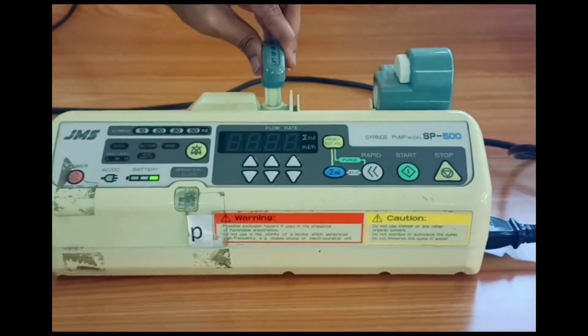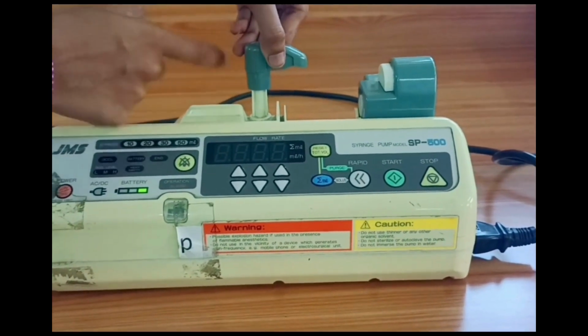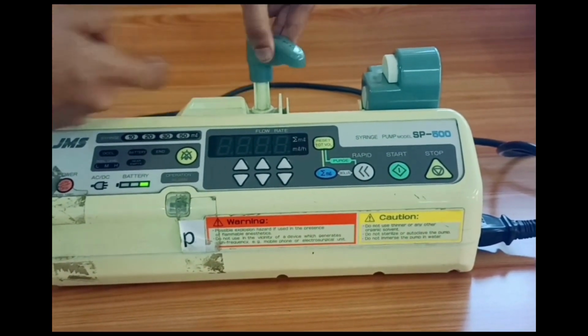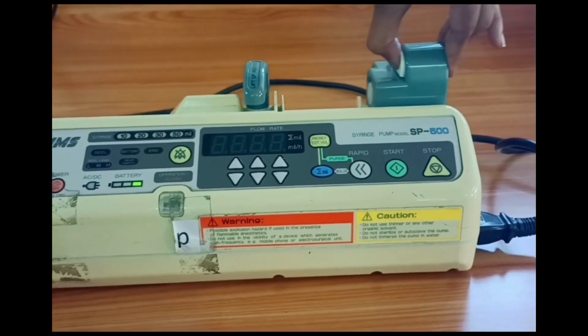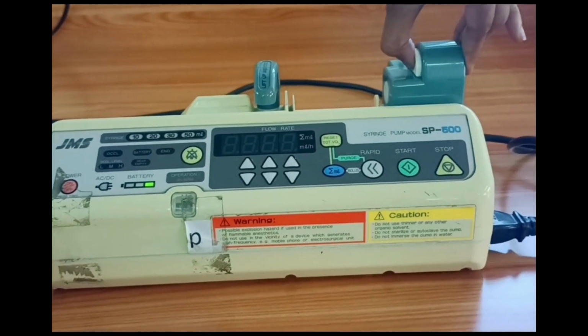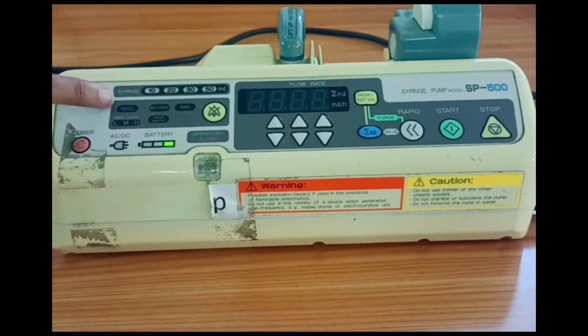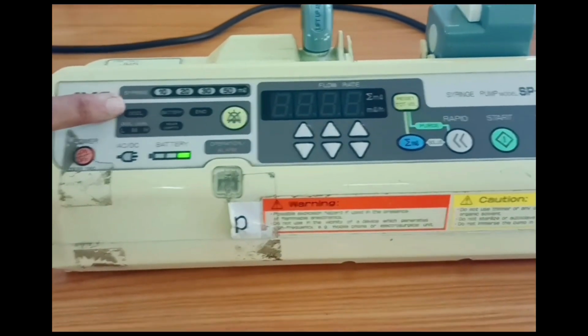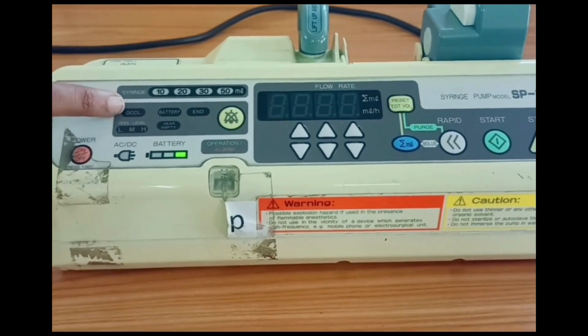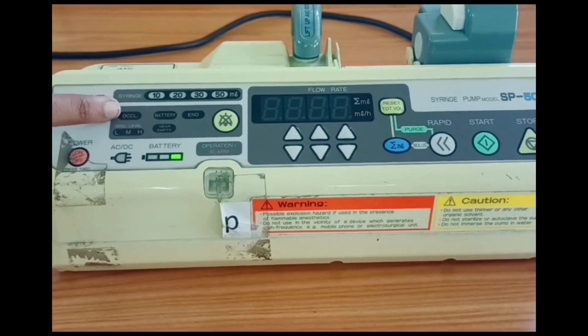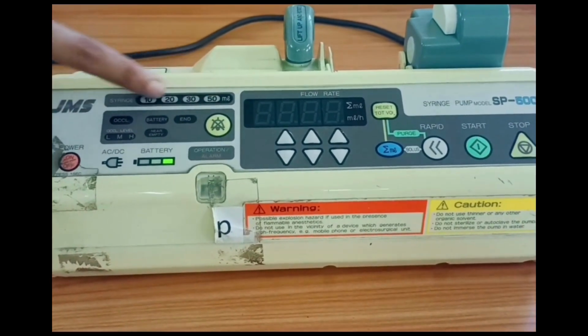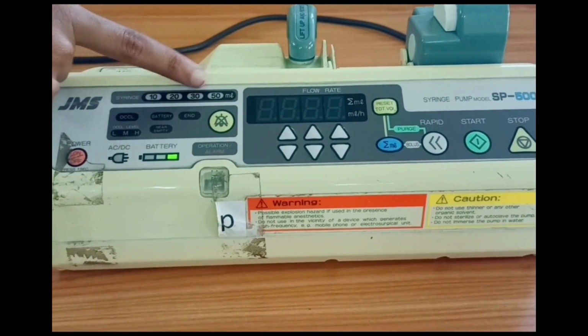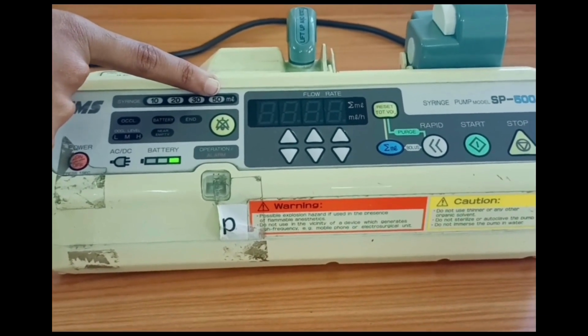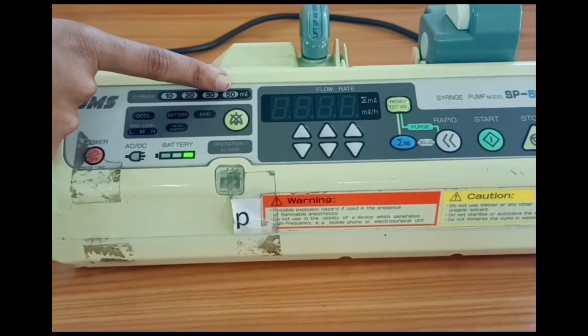Now, let us discuss the parts of the syringe pump. This is the syringe barrel detector, and this is the clamp of the syringe barrel detector. This is the plunger which holds the syringe and it is able to move in and out. Now, let us discuss the displays of the syringe pump. This display lamp flashes when the infusion line is overloaded or the plunger is overloaded. This is the syringe size display. The sizes 10, 20, 30, 50 are displayed. If the syringe is not set properly, all the lamps are going to flash.